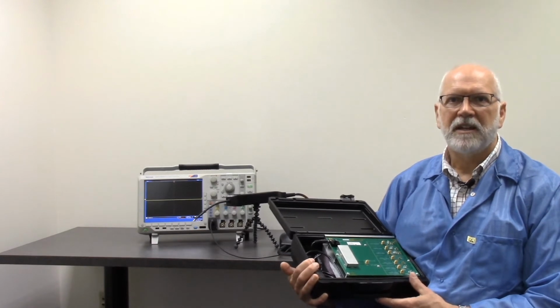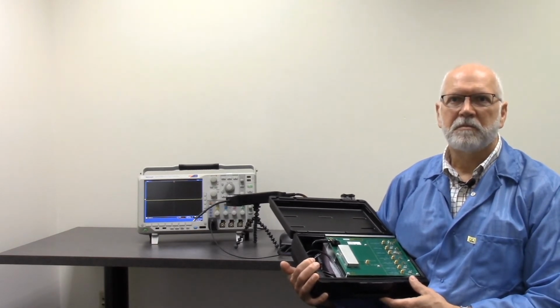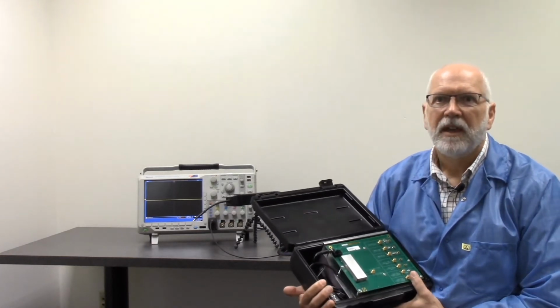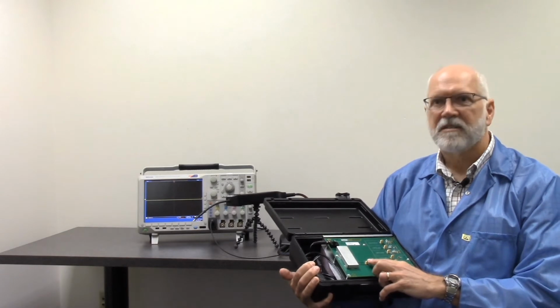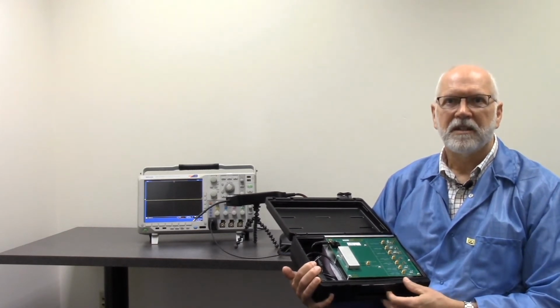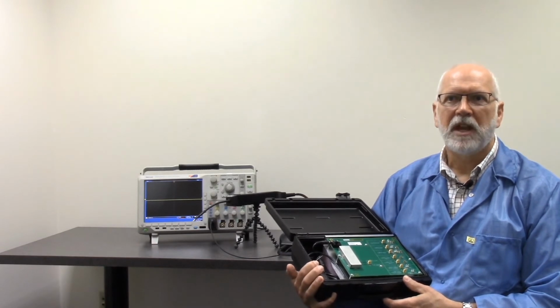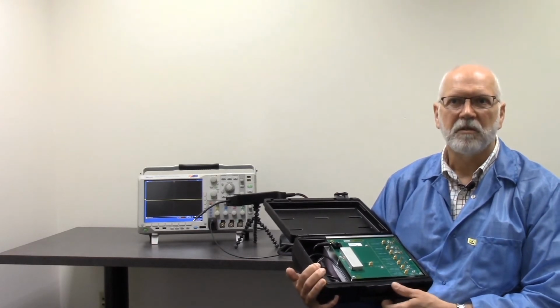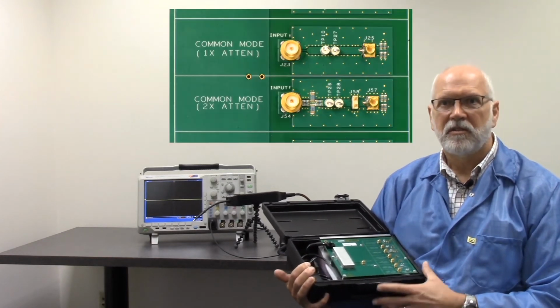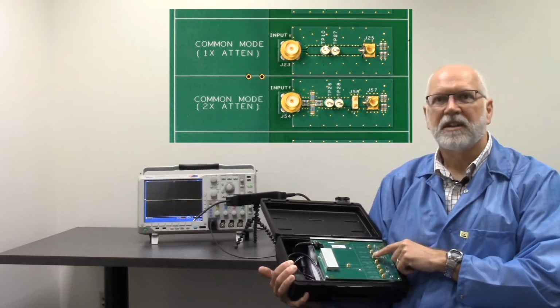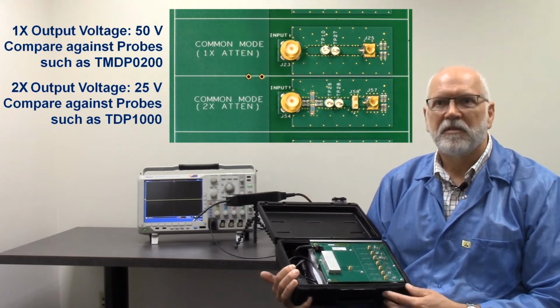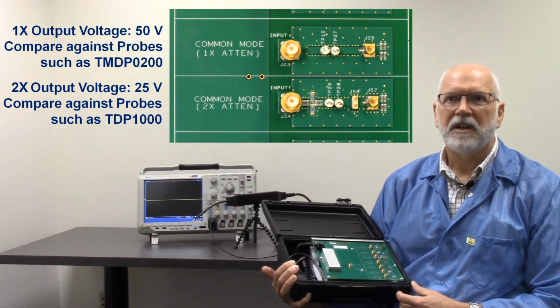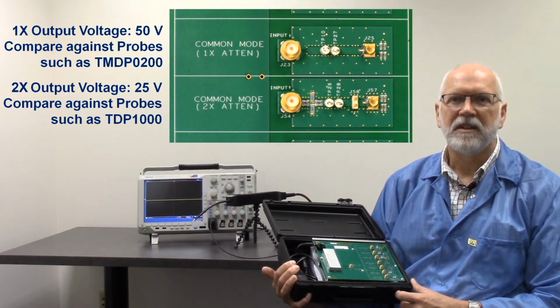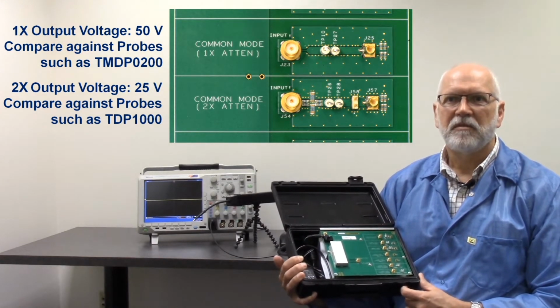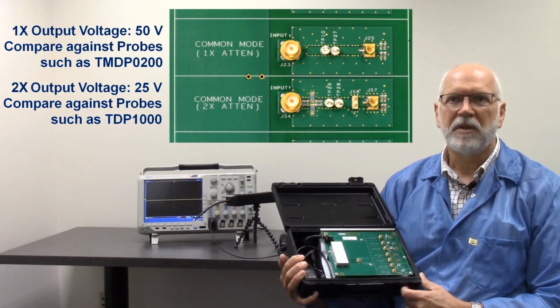The demo board has a fast edge that will allow you to demonstrate the difference in performance between IsoVu and other differential probes. The high amplitude output of the demo board is approximately 50 volts with an edge rate of 500 picoseconds. Because the 50 volt output exceeds the common mode capability of the TDP-1000, which has a 35 volt common mode voltage rating, the demo board includes a 2x attenuation section. The 1x attenuation has an output voltage range of 50 volts, and this part should be used to compare against higher voltage probes such as the TMDP-0200. The 2x attenuation has an output voltage of about 25 volts, and this part should be used to compare against lower voltage products such as the TDP-1000.